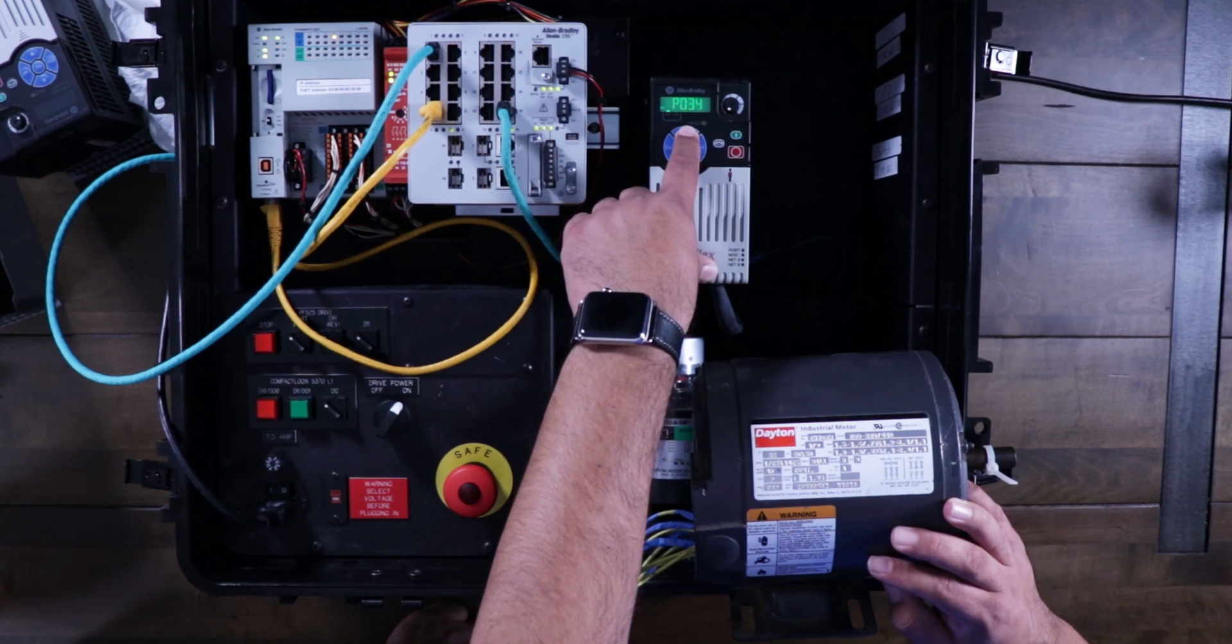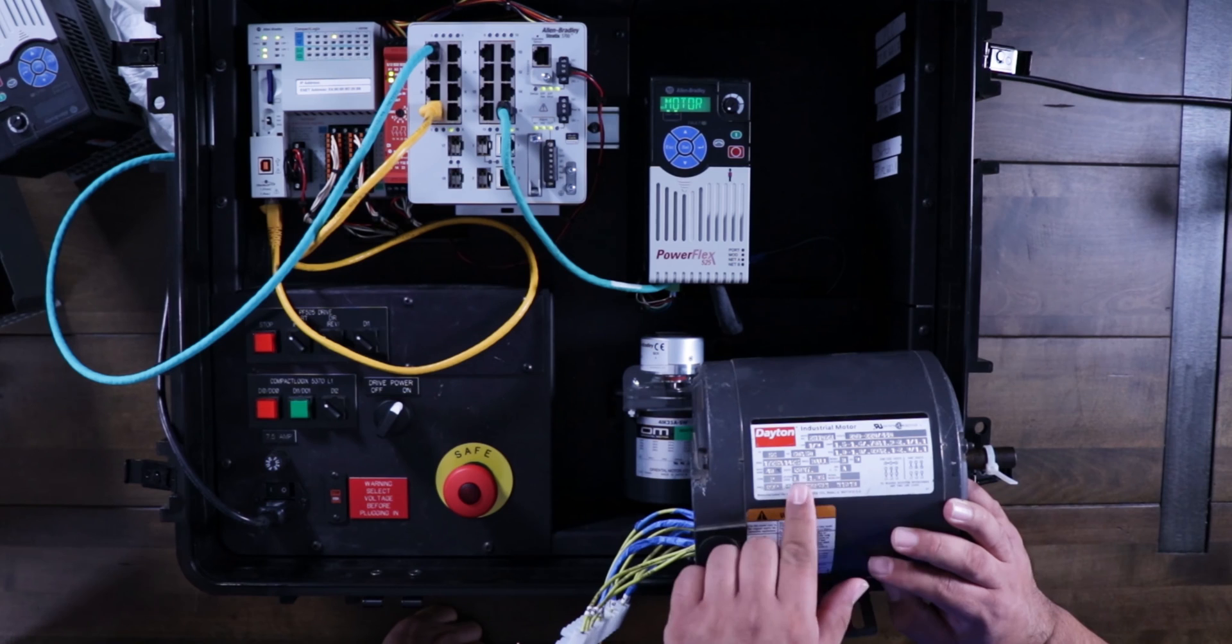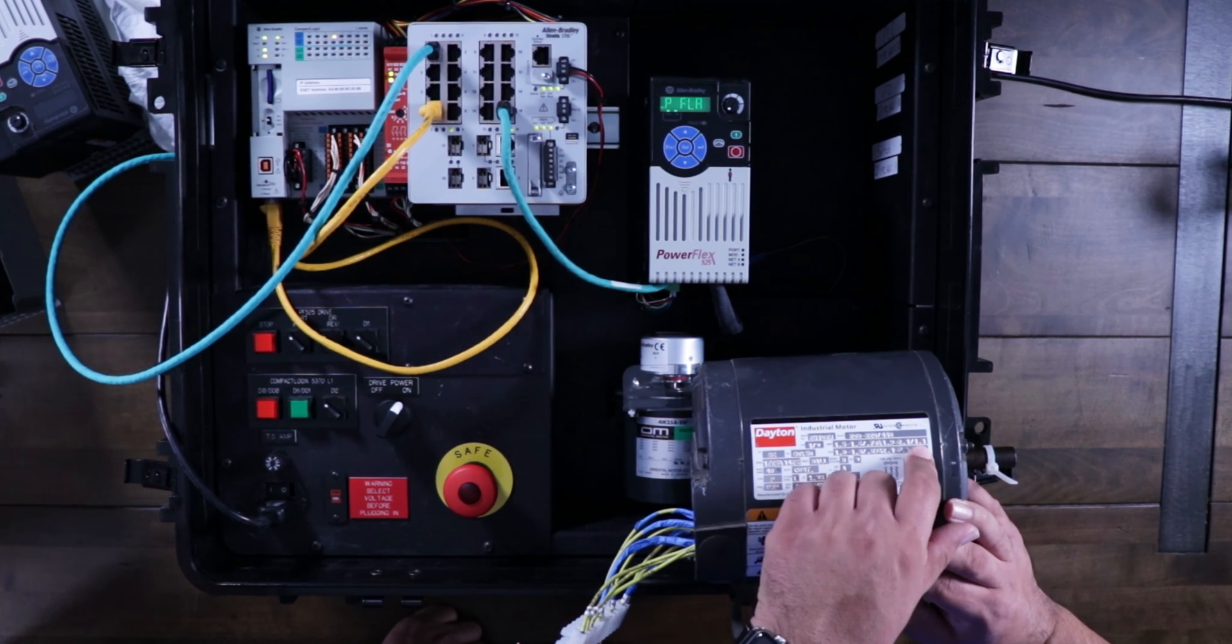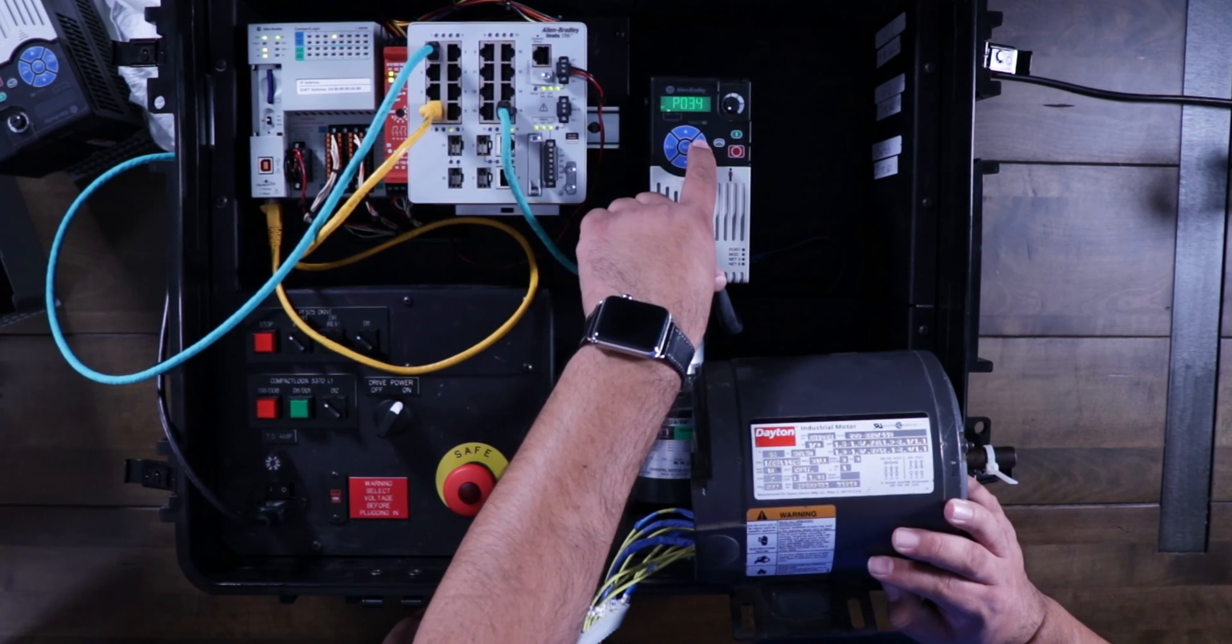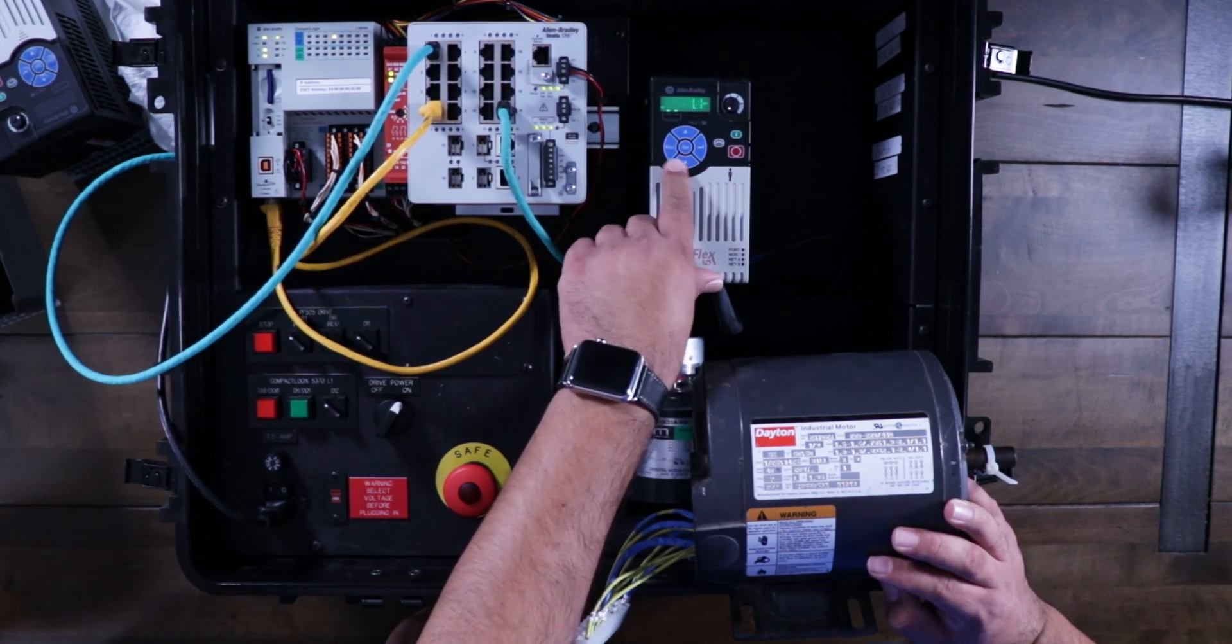So P34, that'll be the full load amps of the motor. And that's taken right off of the motor with no service factor included. This one is 1.1. So we can select that and set it for 1.1.